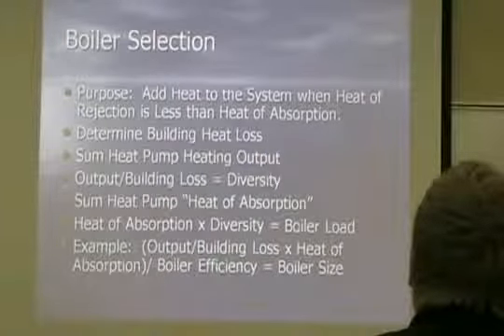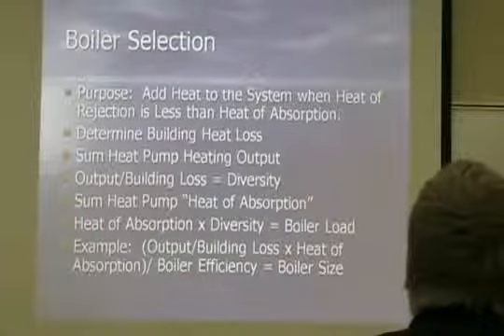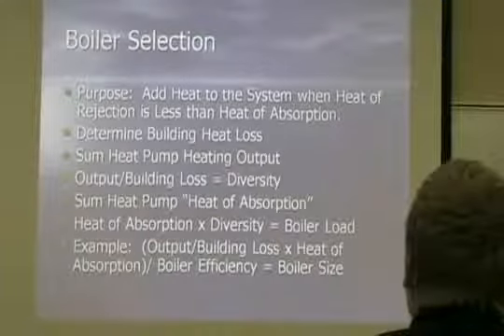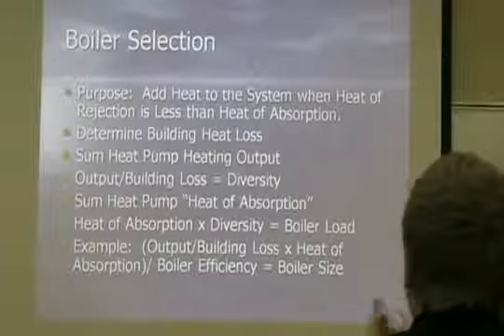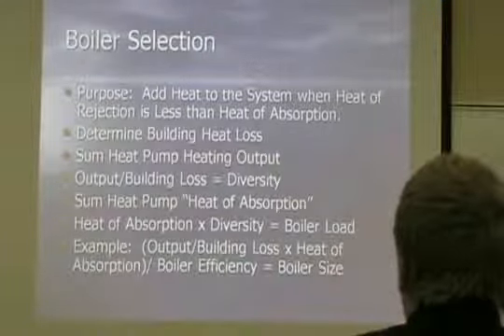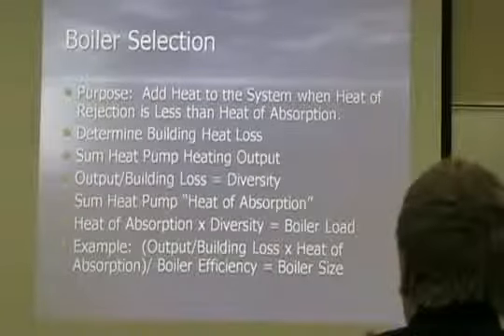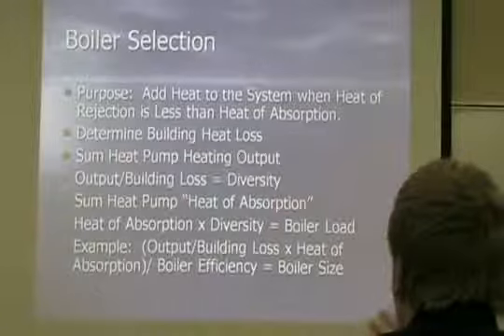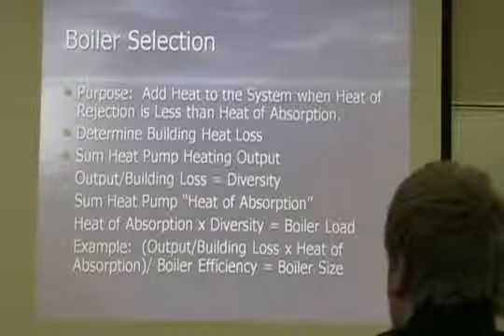Let's talk about the boiler. The boiler is to add heat in the system when the heat of rejection is less than the heat of absorption. We talked about simultaneous heating and cooling. So if all the units, or the majority of the units are heating, they're actually absorbing heat out of your loop and the loop temperature is dropping. So I've got to have a boiler to supplement that loop temperature and raise it back up to my set point, which in the wintertime in water source heat pumps is generally about 60 degrees.